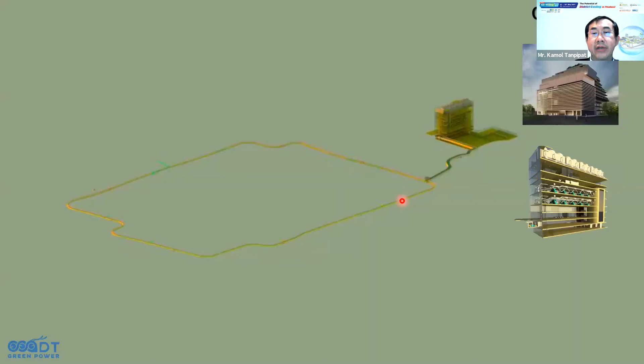Inside the CUP, or central utility plant building, the main service of the building is the district cooling system, which has been designed for a full capacity of 20,000 refrigeration tons, divided into two phases. The first phase will be ready to supply in 2022 with a capacity of 10,000 tons.